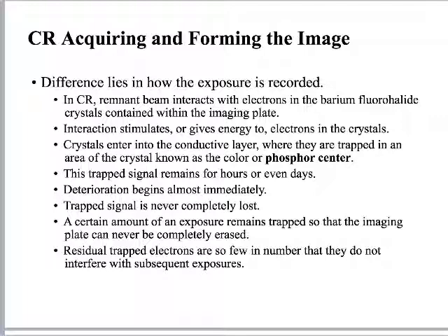Here's what's happening inside the PSP plate when we make an exposure. The x-rays exiting the patient interact with electrons in the barium fluorohalide, and those electrons get trapped in what we call a phosphor center. Think of it like packing bubbles — the x-rays are popping the little packing bubbles inside the PSP plate. From all the bubbles being popped, we're making a picture. We'll somehow unpop those bubbles to read them out.